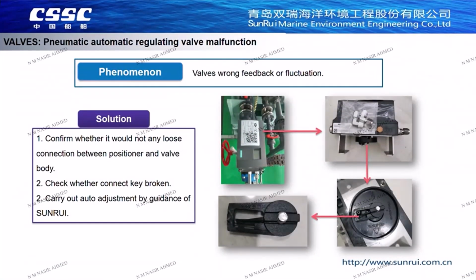If the pneumatic valve position feedback is incorrect or fluctuates badly, in addition to wear inspection, the connecting key at the bottom of the positioner further needs to be checked. The connecting key is damageable and can mislead the position feedback of the valve. If there is no problem with the above, the valve shall be calibrated under the guidance of Sunrui.